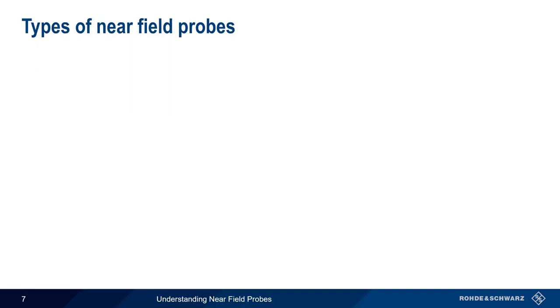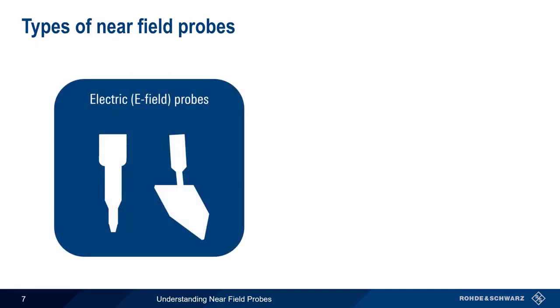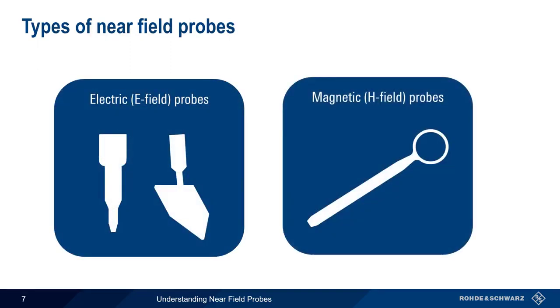Near field probes can be divided into two types, electric or E-field probes, and magnetic or H-field probes. Most near field probe kits will contain both types of probes. These probes are designed to, ideally, respond only to one near field component. Let's start by looking at E-field probes.